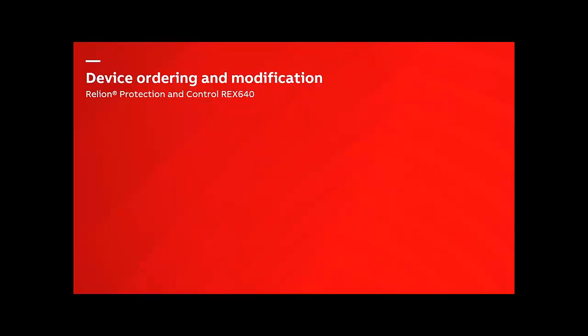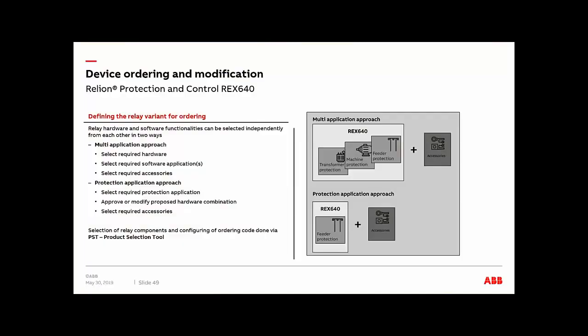So when it comes to device ordering and modification, you're going to have an initial relay that you order, and because it's a modular design, you can always have additional either software protection packages or hardware if needed by your new application. You can always go into the ABB product selection tool and see how the relay would look, how it would be configured as far as space on your back plate. That's available there for you.